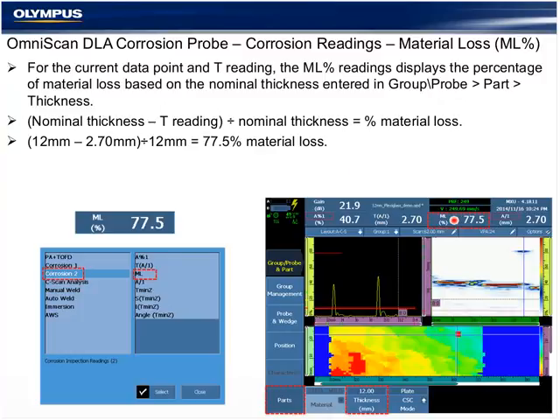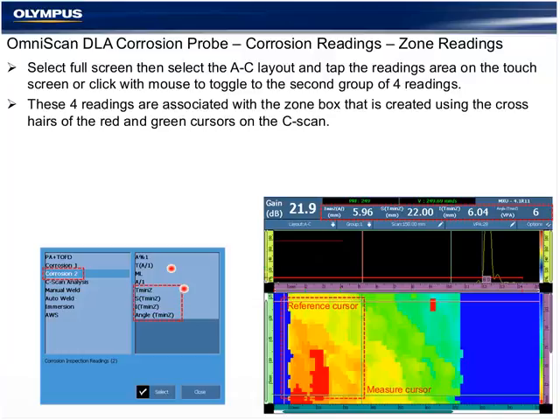the material loss here. Ultimately, that's what the end buyer wants to know about his inspection: how much material is lost. So of our 12 millimeter thickness, the T reading in the gate, based on the gate configuration used to measure it, gives us a 77.5% material loss. Pretty simple math. And then we have a series of readings in the second group of 4. Again, toggling this area on the touch screen, or with a mouse in OmniPC, will switch between the 2 groups.